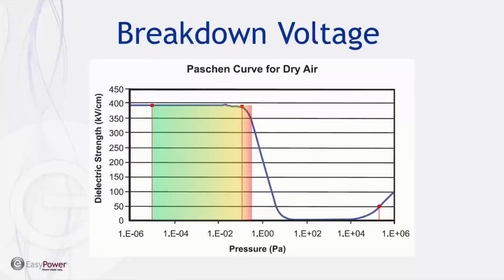So going back to the vacuum, I've got a graph here which is called a Paschen curve. This Paschen curve shows the dielectric strength of dry air, in this case, as a function of pressure and the contact gap. For this particular graph, the contact gap is assumed to be 1 centimeter or 10 millimeters. And you have pressure on the x-axis. I have a few red lines here for reference. On the far right is atmospheric pressure, around 1 times 10 to the positive 5, or 100,000 Pascal.